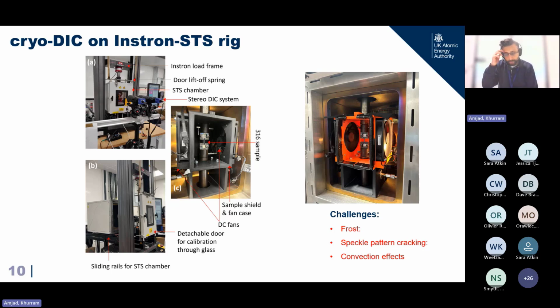And the other challenge with regards to DIC is that, for example, if you're testing a material like 316, which remains very ductile even at cryogenic temperature, we are talking about up to 50% gauge extension. So you start getting your speckle pattern cracking, and the speckle pattern acts as a strain witness. If it starts to debond, then your strain measurements are essentially useless. So we have to develop a technique where we can do a speckle pattern which can stretch up to 50-60% without cracking.